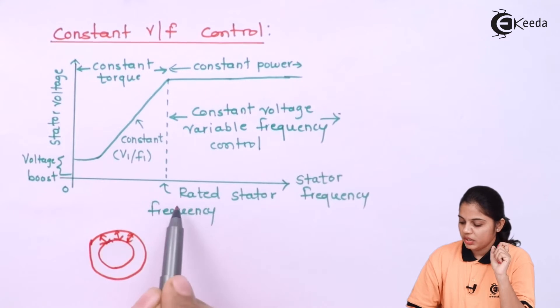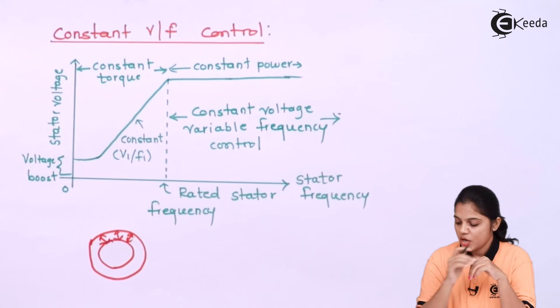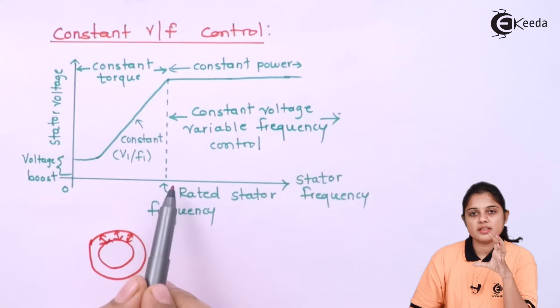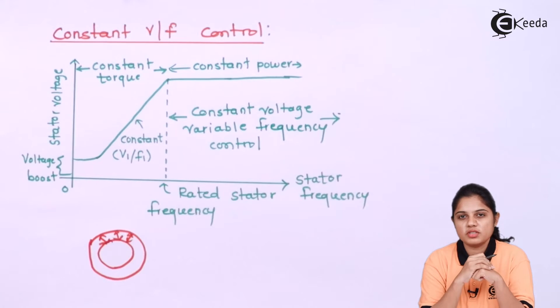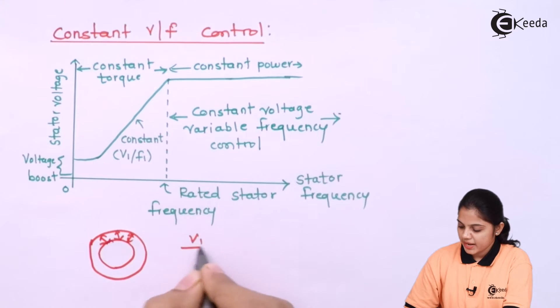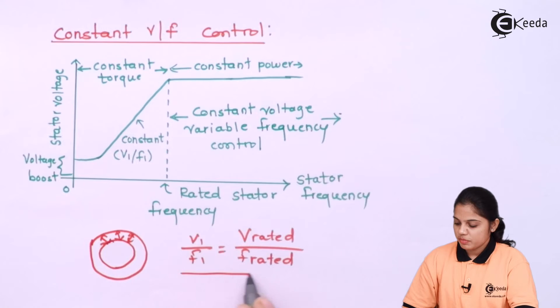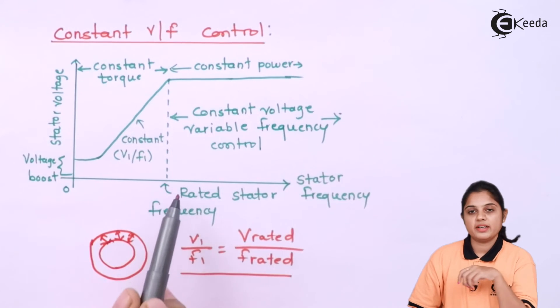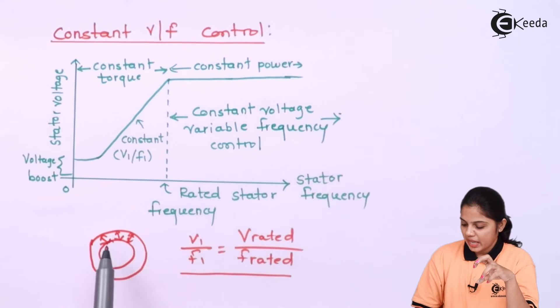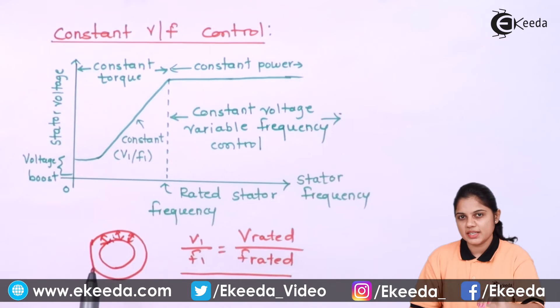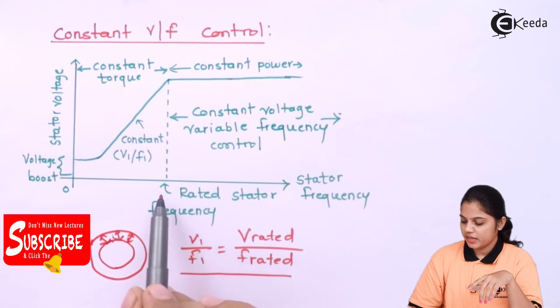This will happen only up to the rated stator frequency — a critical speed value. Beyond this, with constant voltage and variable frequency control, you will achieve constant power. Up to rated stator frequency, V1/F1 equals V-rated over F-rated. After that, the air gap flux between rotor and stator starts decreasing, so torque decreases, but power remains constant.